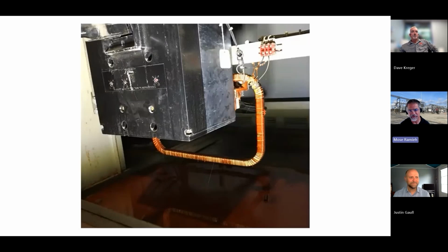But from a safety standpoint, and I'll let Dave speak to this a little bit too, what we have here is, one, we've got metal. Now it is still insulated, but it's laying on the buswork in the back here, so that's a potential failure point, as well as there's no assurance that the ground fault protection system in this gear will work. And once again, this could have been identified with systematic maintenance on an every 2-year, every 3-year rotation and headed this off, because it just doesn't melt all at one time. It's a process. But Dave, what else?